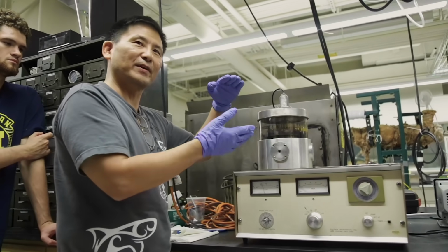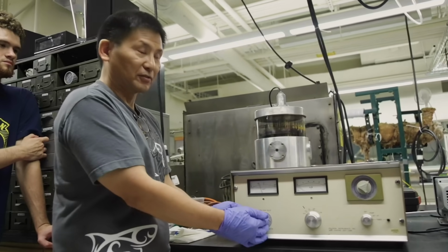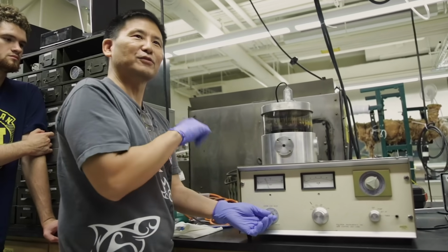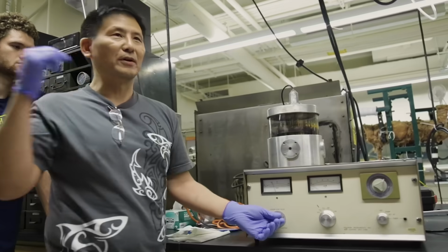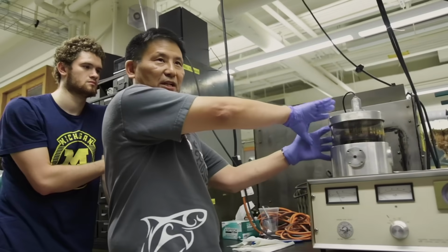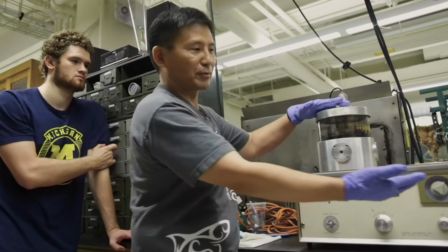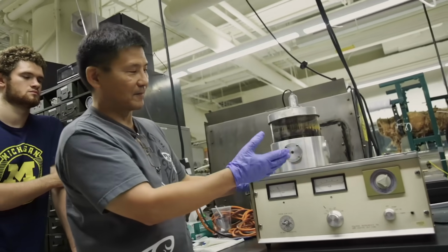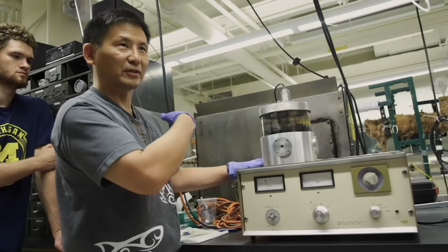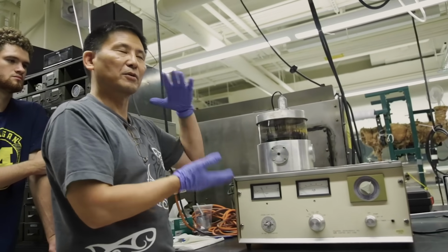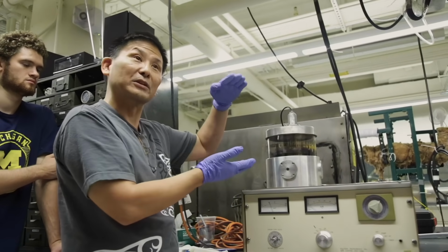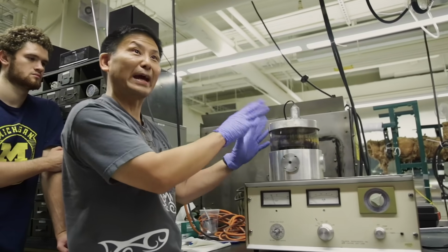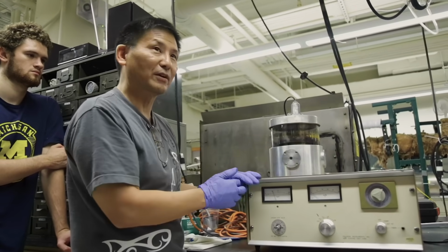But then it has to get fed, so with this little knob here I was feeding it argon. The argon bottle from over here is going into this chamber. When you're feeding the argon in, the pressure comes up. If the pressure comes up too high on this particular instrument, it has an automatic cutoff where the high voltage cuts out, because one of the reasons why it works is that we have so few atoms in there, measured by that.